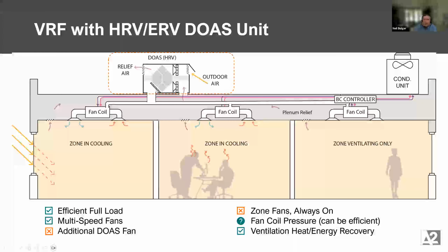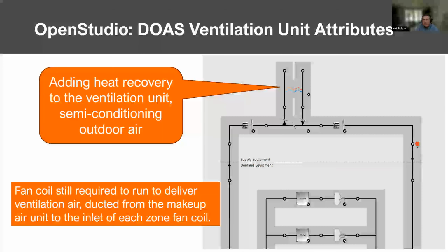Keep going. If we had a dedicated outside air system, we're now recovering heat, take some more pressure. We've got to put a bigger fan on the DOAS unit to push the air through that system. So we've now built this system out, right? We've added heat recovery to the model. This model's configured to a very basic set point. It's just always trying to hit 62 degrees delivered to the space. And you could go into some more modeling if you wanted to do some preconditioning or avoid very cold conditions. Today, I kind of left it basic.